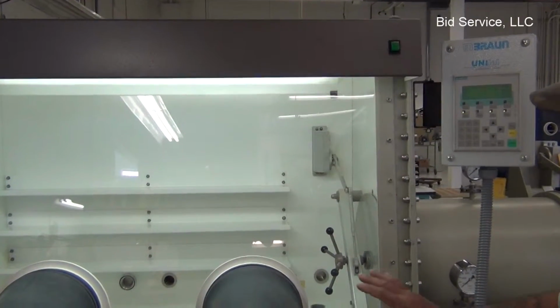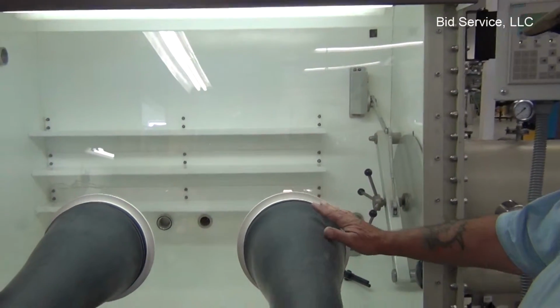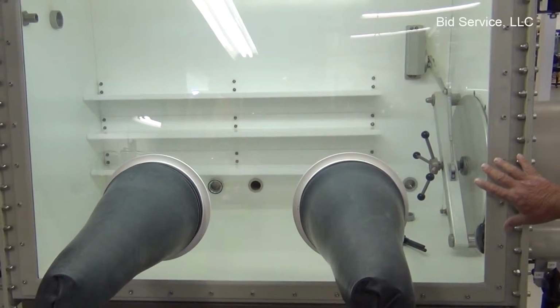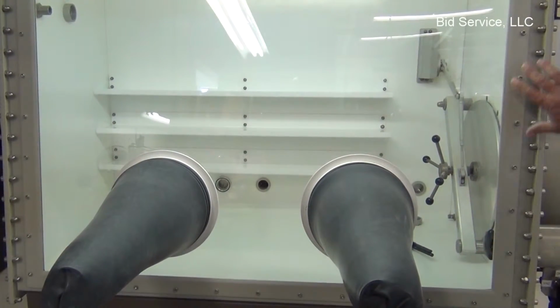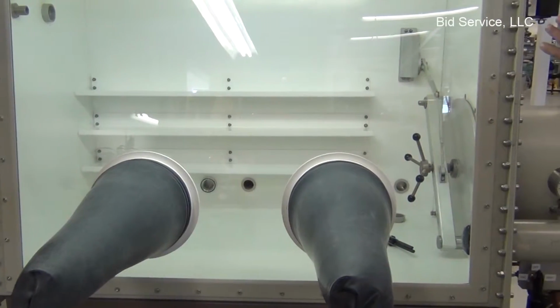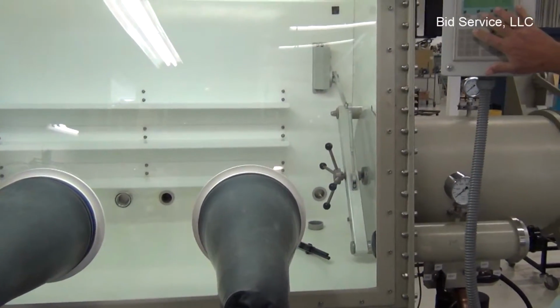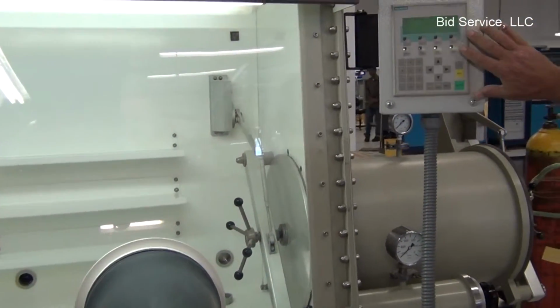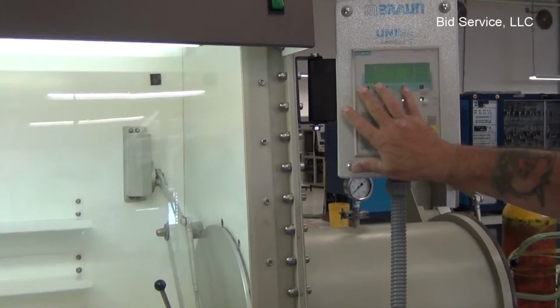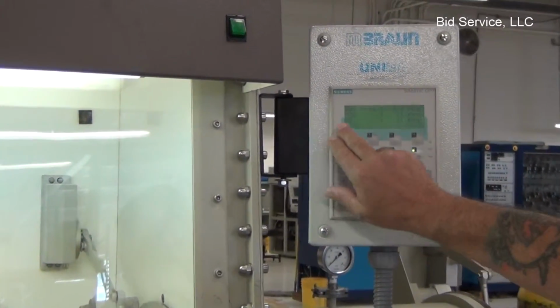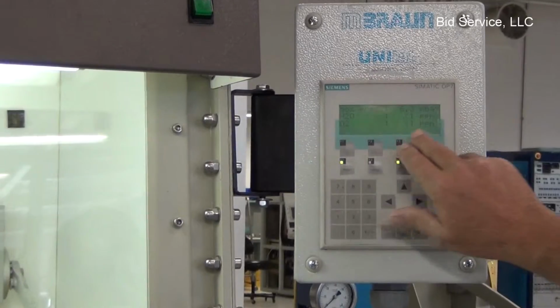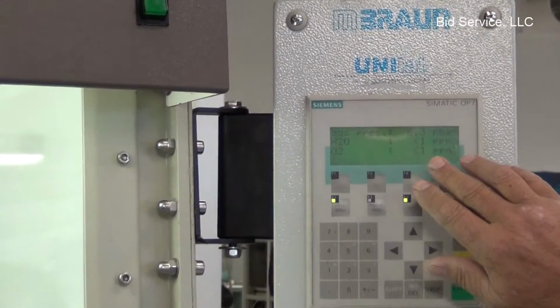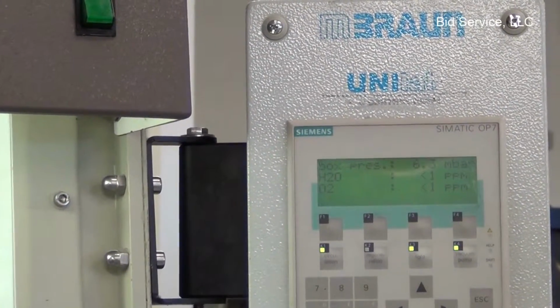Okay, here we have an MBraun glove box. We've installed new gloves. Interior's been all cleaned up. If you look at the display, you can see we've got a 6 millibar pressure right now. What I really want to show here is that our moisture and our oxygen content is less than 1 ppm. The sensors are on the back, I'll point them out.